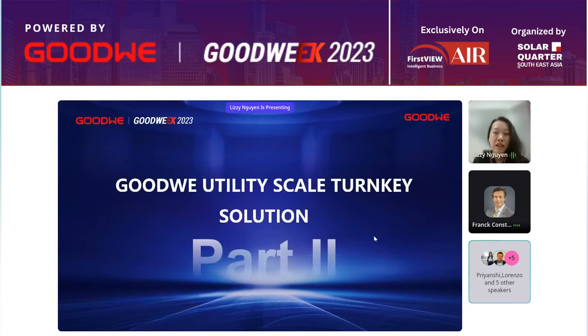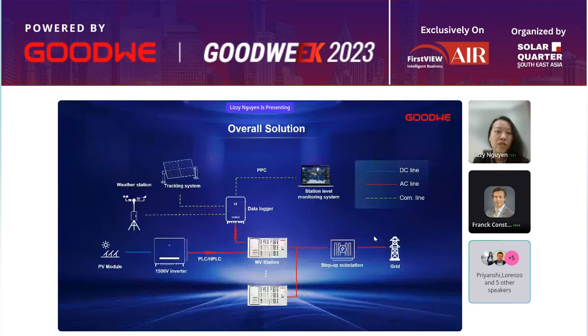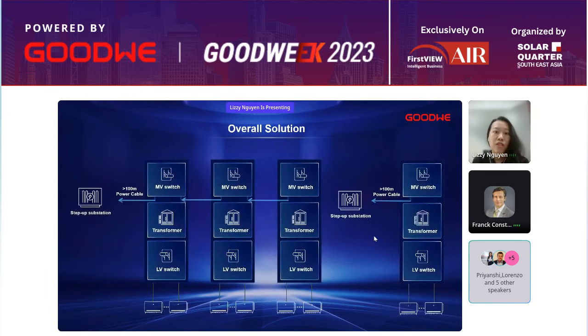Let's go to our utility scale string inverters. This is our overall GoodWe utility solution, featuring 1,500 volt inverters together with the MV station and our data logger SCU 3000. The MV station is a combination of the transformer, the MV switch, and the LV switch, which can be connected to the step-up substation with a power cable more than 100 meters. We can connect up to three MV stations at the same time.